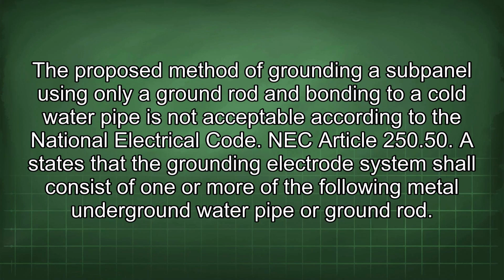The proposed method of grounding a subpanel using only a ground rod and bonding to a cold water pipe is not acceptable according to the National Electrical Code. NEC Article 250.50 states that the grounding electrode system shall consist of one or more of the following: metal underground water pipe or ground rod.